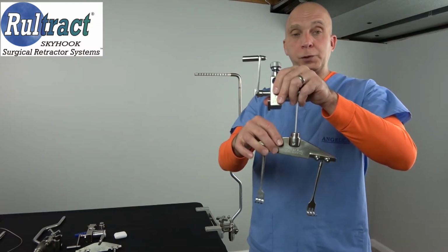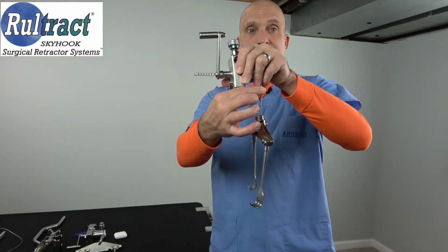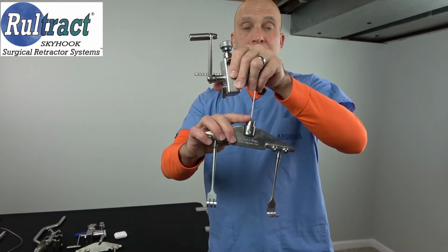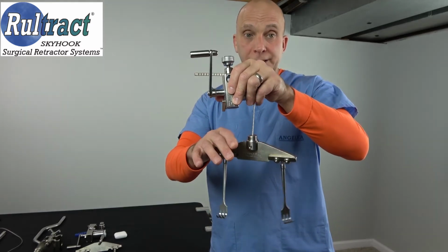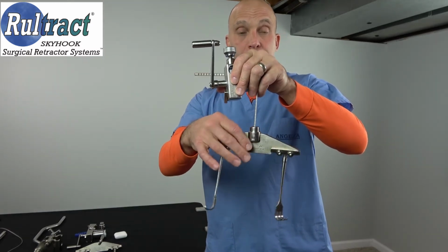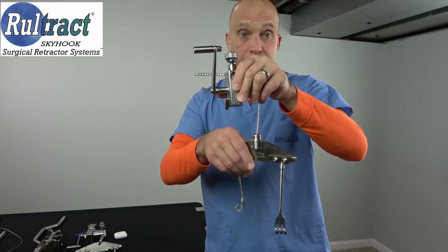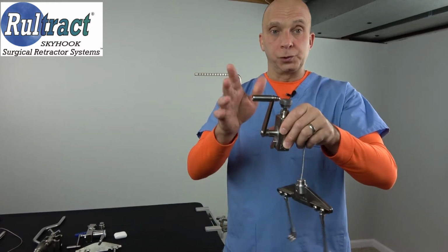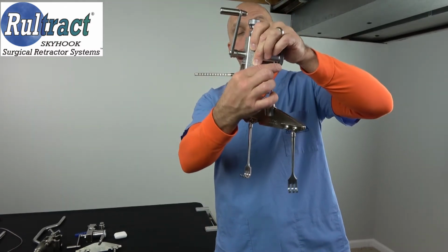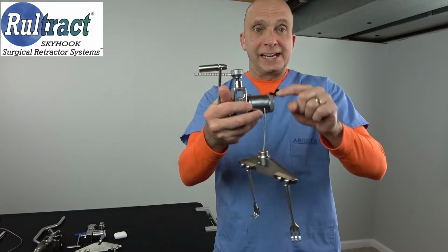Now, the first thing to note here is that your rake plate is held onto your cable by a hub. This is an older design, and in this situation, we do not remove this rake plate from the cable for cleaning and sterilization. So step one for you is going to be to pull this cable down out of the spool.